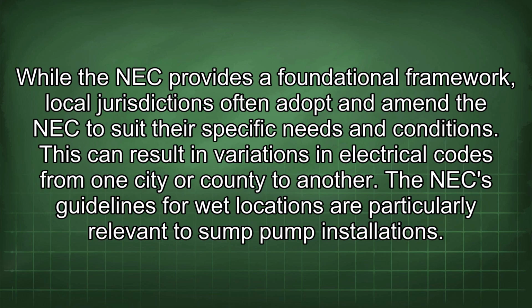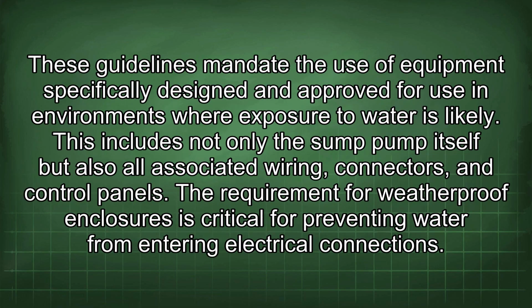The NEC guidelines for wet locations are particularly relevant to sump pump installations. These guidelines mandate the use of equipment specifically designed and approved for use in environments where exposure to water is likely. This includes not only the sump pump itself, but also all associated wiring, connectors, and control panels.